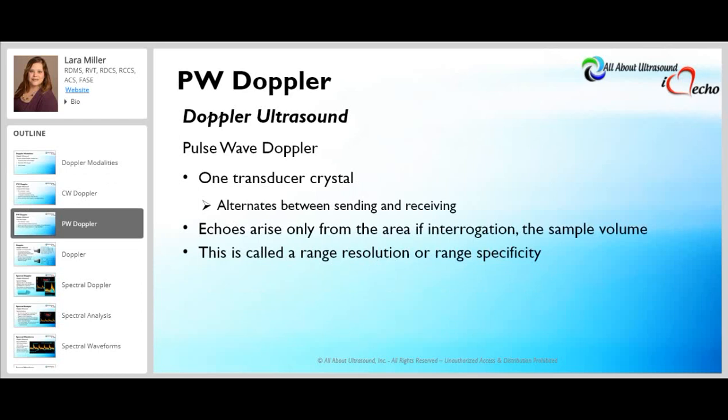With pulsed wave Doppler, it works on one transducer crystal, and so it alternates between sending and receiving. The echoes arise only from the area of interrogation, or the sample volume or sample gate. Because of this, there's range resolution or range specificity, which eliminates the range ambiguity artifact. However, it does display a lower spectrum of velocities, and so aliasing can be an artifact that occurs with pulsed wave Doppler.